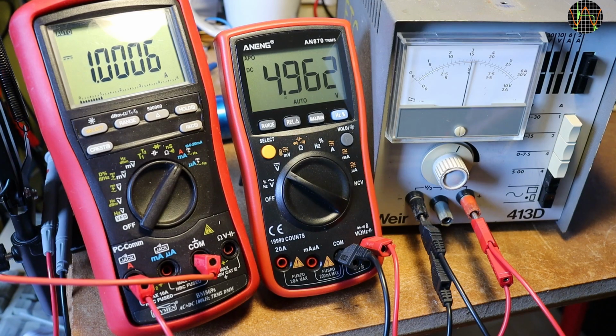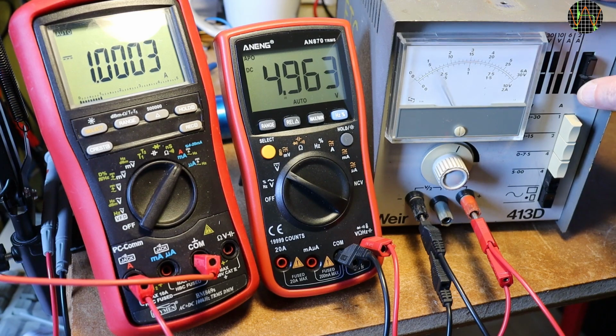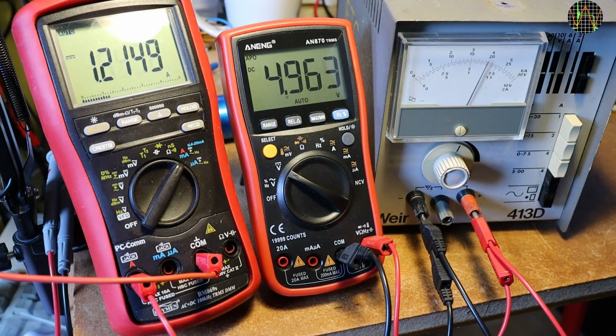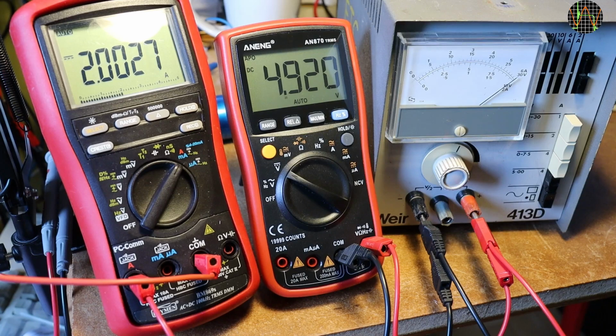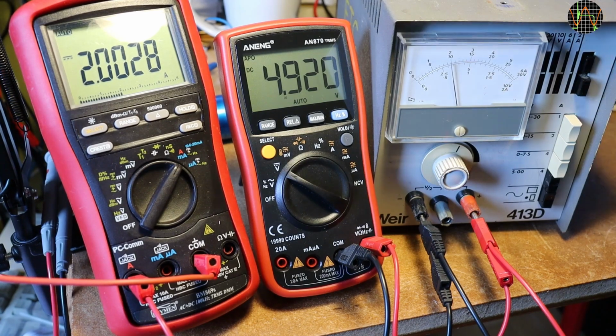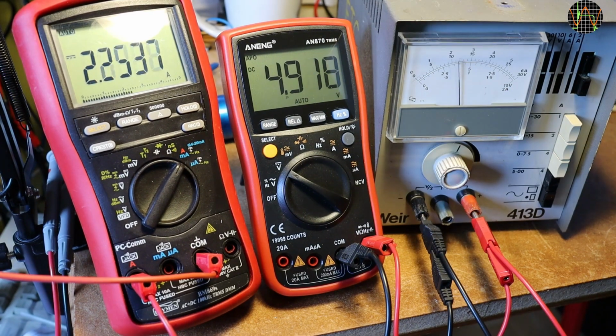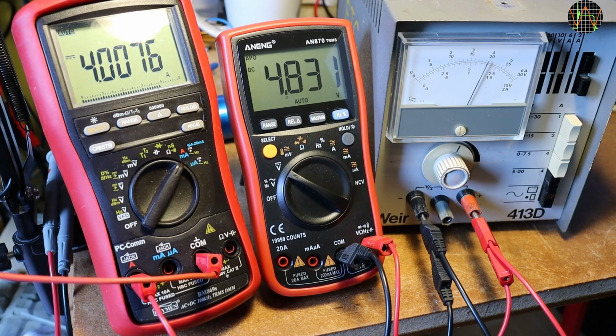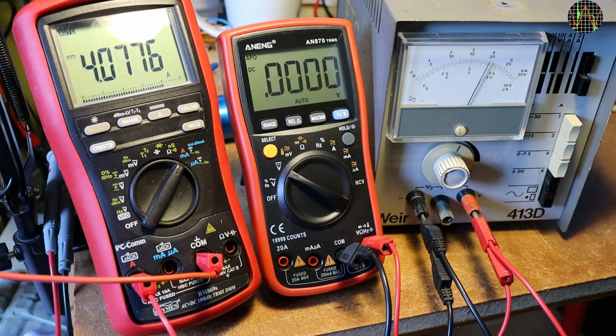5 volt range and 1 amp load. It shows 1 in a 6 amp range as you would expect, and 1 in a 2 amp range. Increasing the current to 2 amps, and it now shows full scale in the 2 amp range and 2 in the 6 amp range. Going all the way to 4 amps and the meter is maybe a tad below 4, but I can live with that. Of course, trying to exceed 4 amps triggers the current limiter, collapsing the voltage.